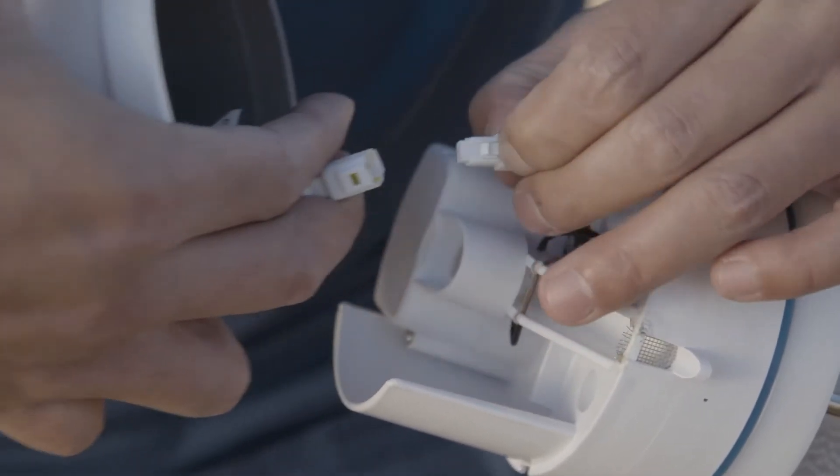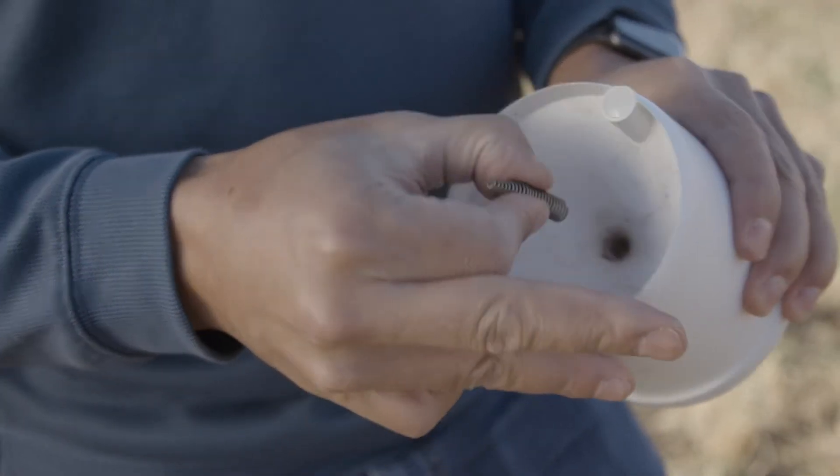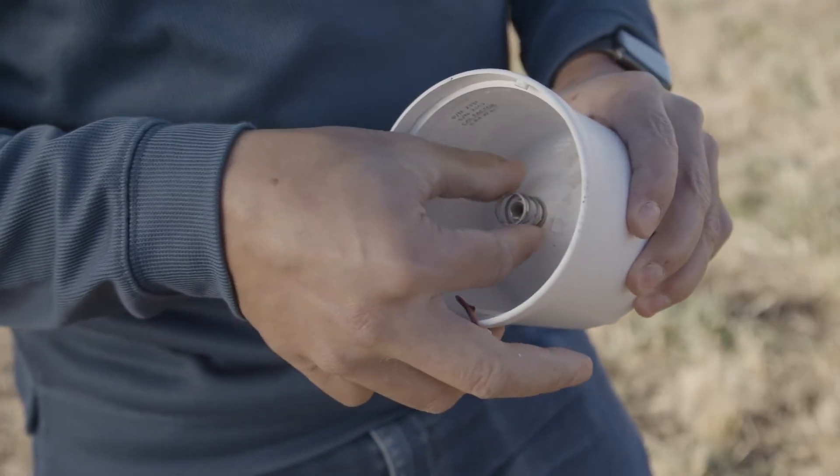Disconnect the pyranometer cable. Remove spring from the top of the funnel. Remove spring from the bottom of the funnel.